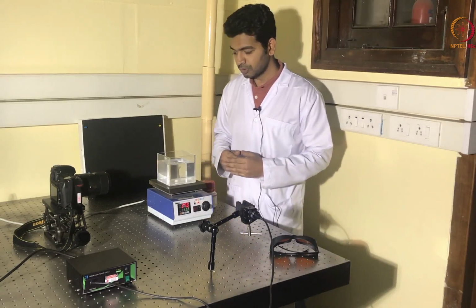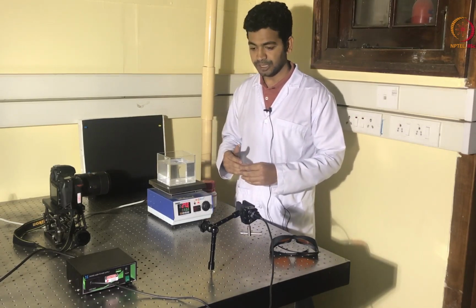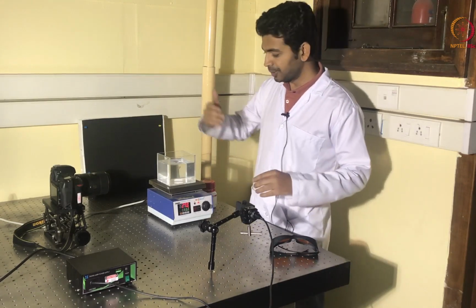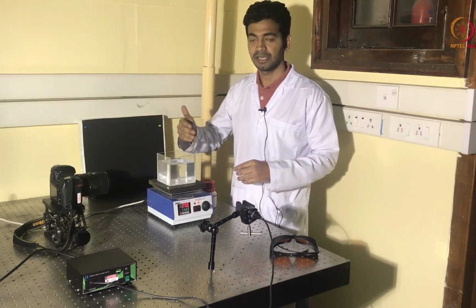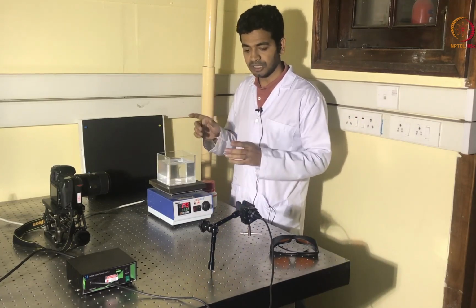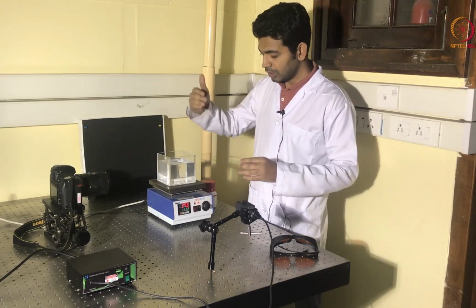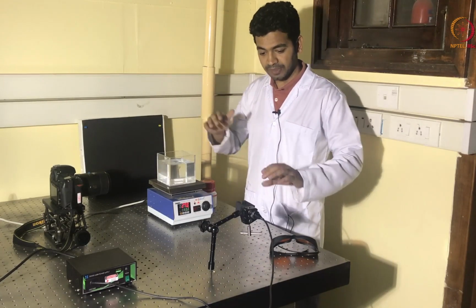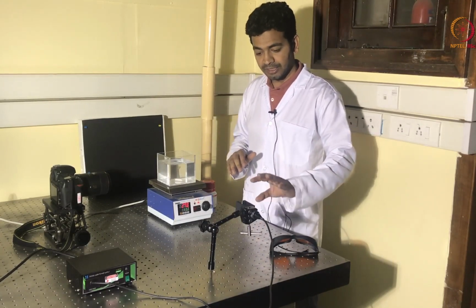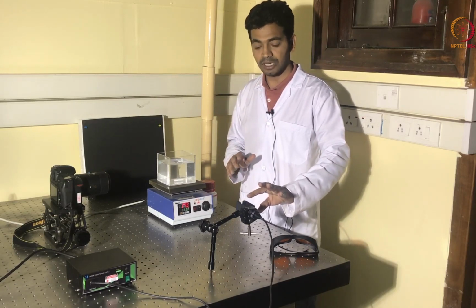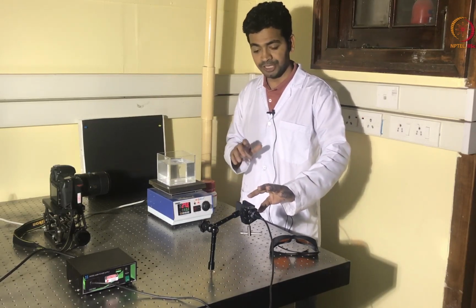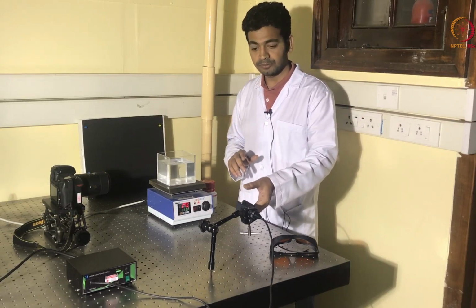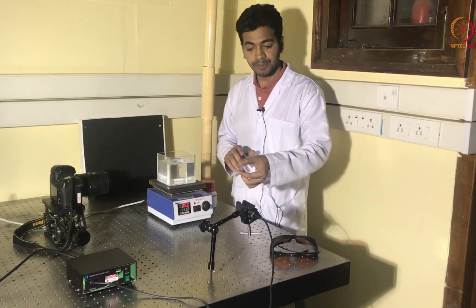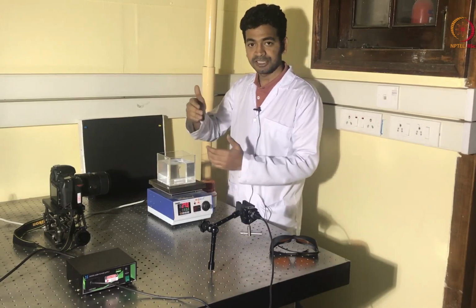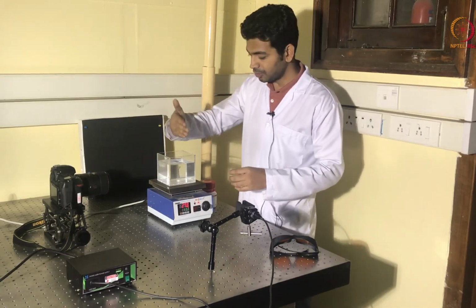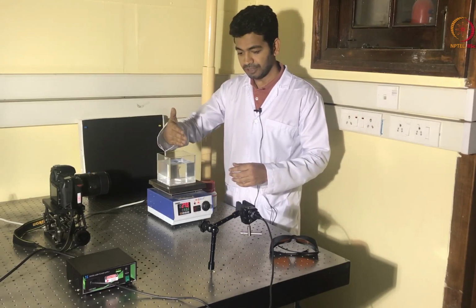Now, to do particle image velocimetry, you need to illuminate your plane of interest in which you want to see how tracer particles are moving. So, to illuminate a particular plane, I have kept a laser here and then a cylindrical lens, which I have earlier demonstrated in the previous video. This cylindrical lens transforms a cylindrical beam of light into a diverging sheet of light. That sheet of light illuminates particles in a particular plane.